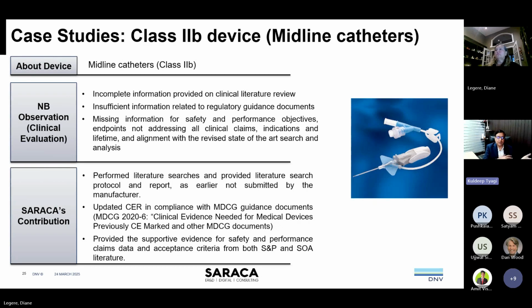When you write the CER, obviously you are going to write the CEP, so make sure that both documents are connected to each other. And also keep in mind that notified body reviewers are reviewing a lot of documents, so you have to make their life a little bit easier so that they understand your document easily. Don't make it too big and too short. Also, it should be really, really nice for them to understand what they're doing, as per the regulation. And that way you will have your report and results come quite quickly and with fewer observations.